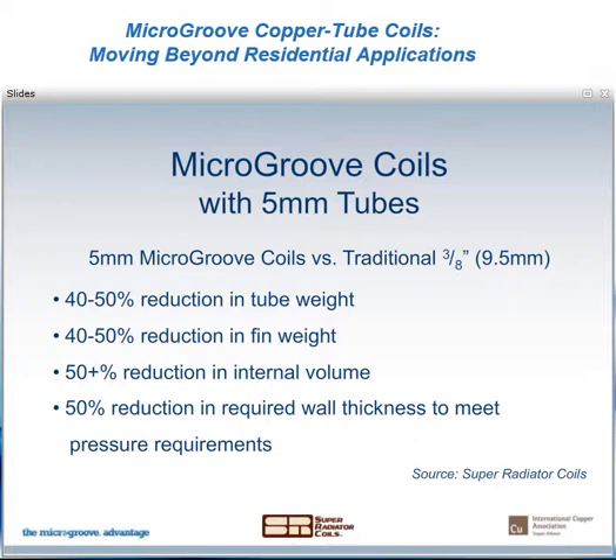But the economic argument behind the movement toward 5 millimeter tubes is certainly a strong one. And we can see in this information supplied by Super Radiator Coils that reductions in fin and tube weights can be as much as 50%. And the reduction in the internal volume can be even more than 50%. And that means considerably lower refrigerant charge.